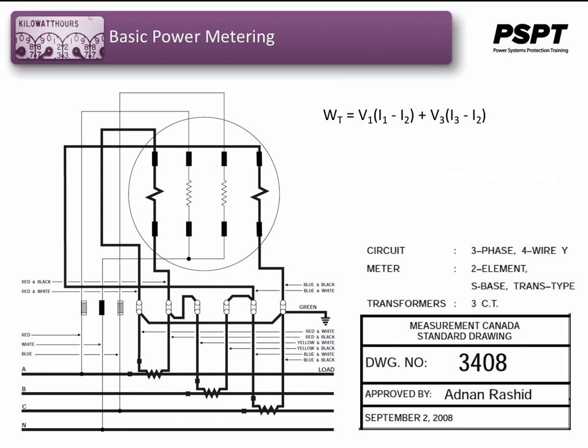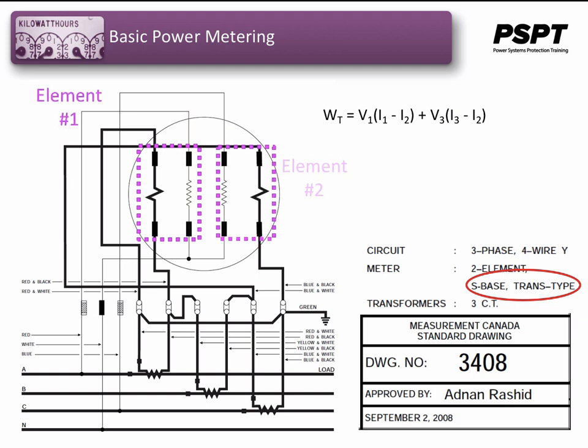The standard 3408 is the same type of metering, only this time we're using an S-base meter, which is a socket or plug-in type metering. The elements look like they're turned sideways, but this would be element number 1, and this would be element number 2. However, all the connections and CTs feeding the meter are the same as before for the A-base meter.